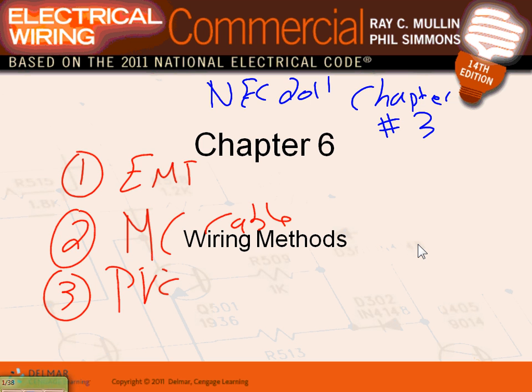Any commercial wiring system. A couple of things I want to tell you. Each one of these has its own article. So, EMT conduits, let's talk about EMT conduits. The advantage of wiring with EMT conduit is you can pull as many conductors as you are allowed to. So it allows you future expansion. Using a conduit will allow you future expansion. So most of the time, you're going to use EMT conduits for feeders, definitely feeders and home runs.